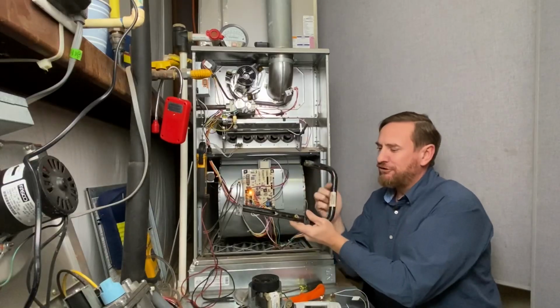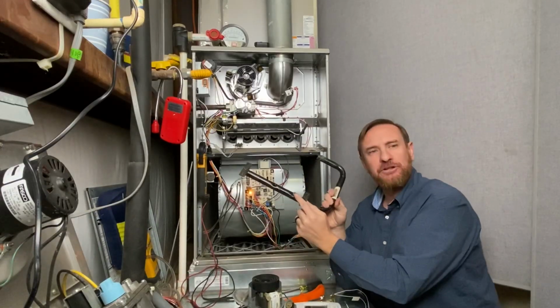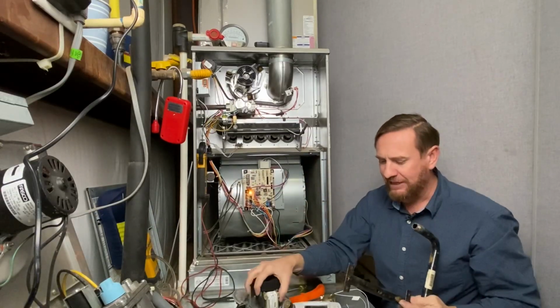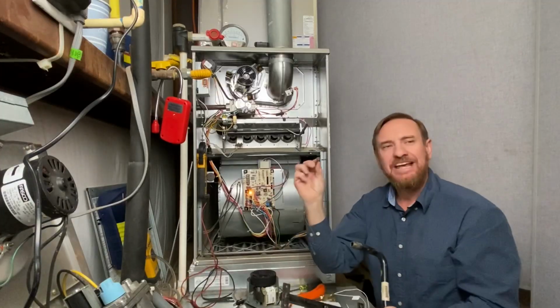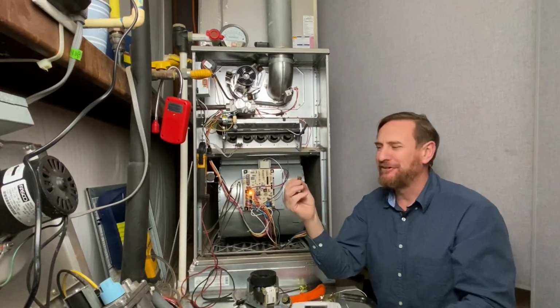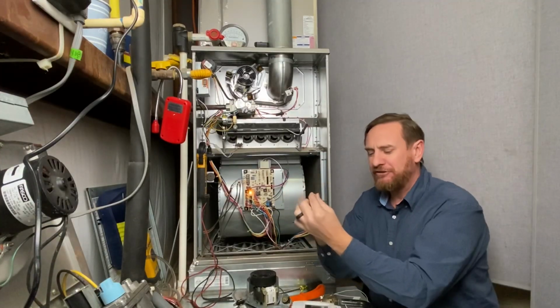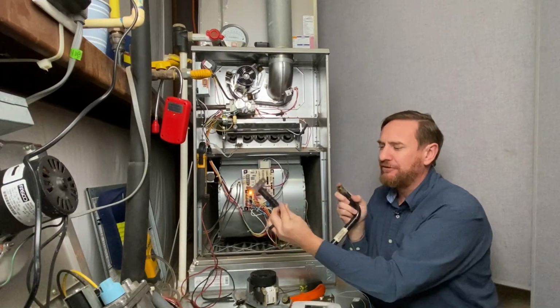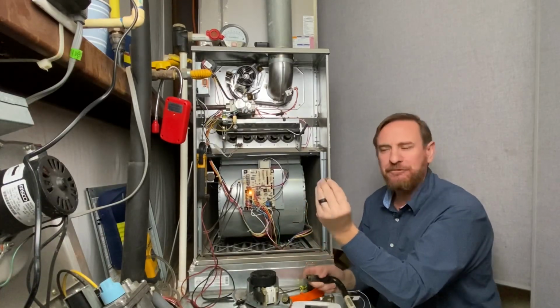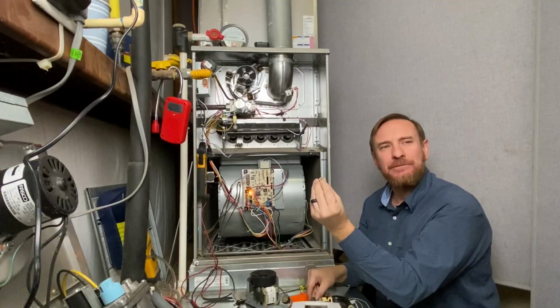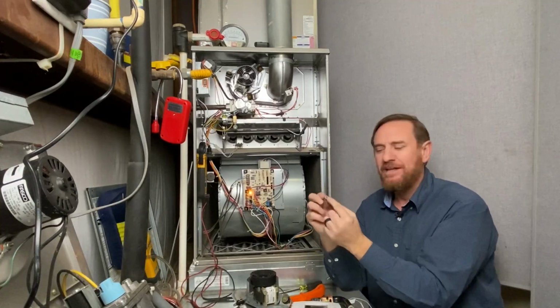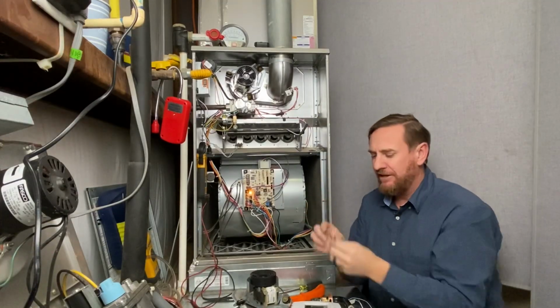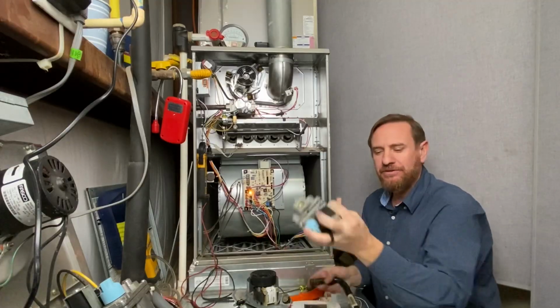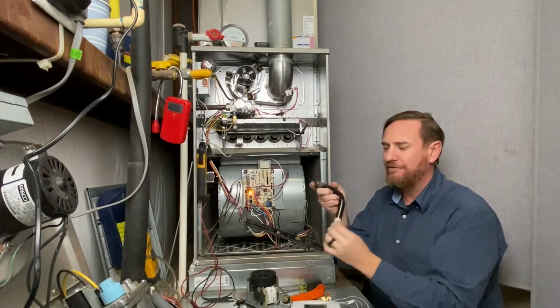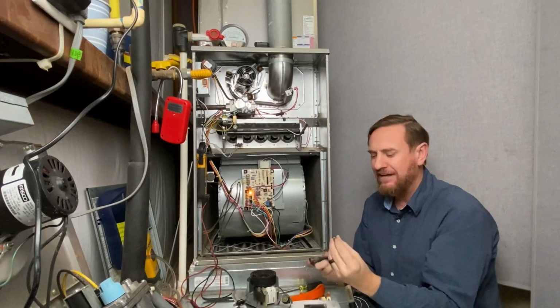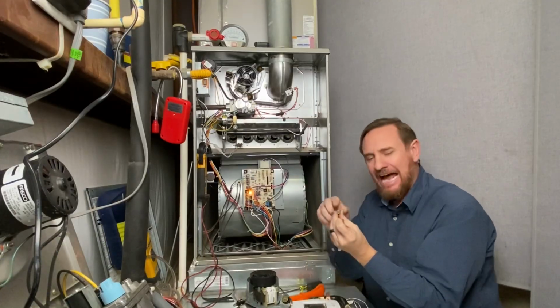So gas flows through the manifolds, then it's going to go to this little component right here. And what I've done is I've taken one of these off, and this is called a spud. I have no clue why they call it a spud, but it's called a spud. And these spuds screw into the manifold. There's a number stamped on here. This particular one's 44. That number is the size of the hole. Another word for hole is orifice. So gas flows through the combination gas valve into the manifold, to the spud, and through the orifice. Now it's shooting gas out of this orifice.